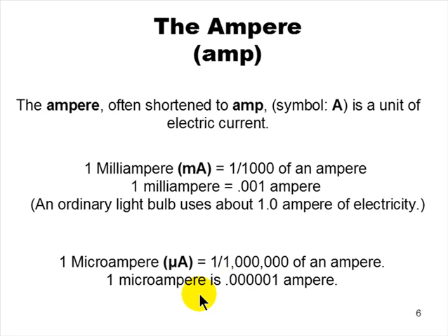Where do we use microamps? Heck, we use microamps all day long. We use microamps for probably most flame sensors you're going to deal with. You know, you want 4 microamps or 5 microamps out of that flame sensor. That's the signal the electronic circuit board is looking for to prove the flame. But it wouldn't matter if it was a capacitor, and that was microfarads, whatever. Micro anything is 1/1,000,000th of something. Milli anything is 1/1,000th of something. Why am I telling you this? They're going to ask on a test.